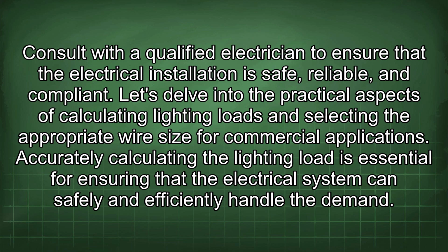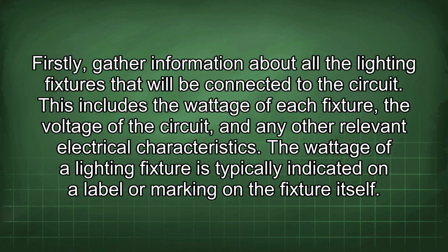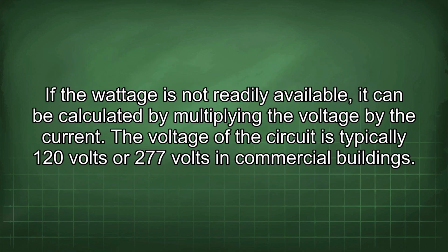Let's delve into the practical aspects of calculating lighting loads and selecting the appropriate wire size for commercial applications. Accurately calculating the lighting load is essential for ensuring that the electrical system can safely and efficiently handle the demand. Firstly, gather information about all the lighting fixtures that will be connected to the circuit. This includes the wattage of each fixture, the voltage of the circuit, and any other relevant electrical characteristics. The wattage of a lighting fixture is typically indicated on a label or marking on the fixture itself. If the wattage is not readily available, it can be calculated by multiplying the voltage by the current.